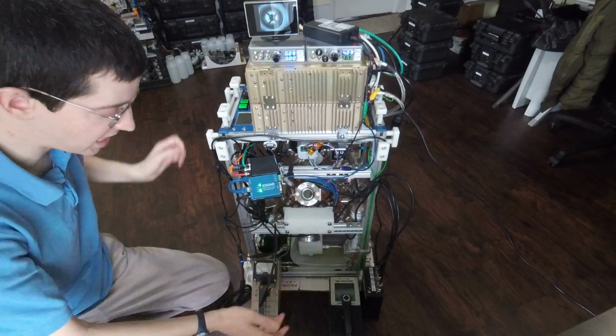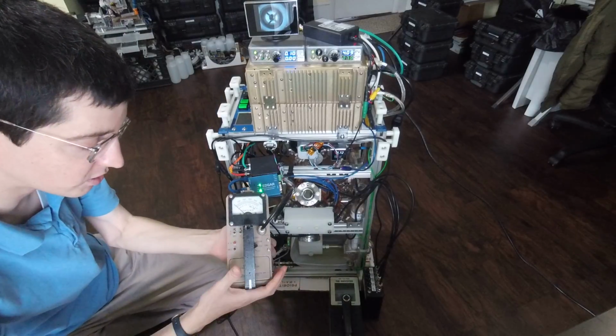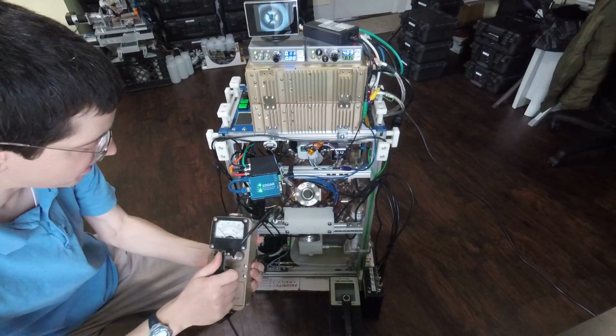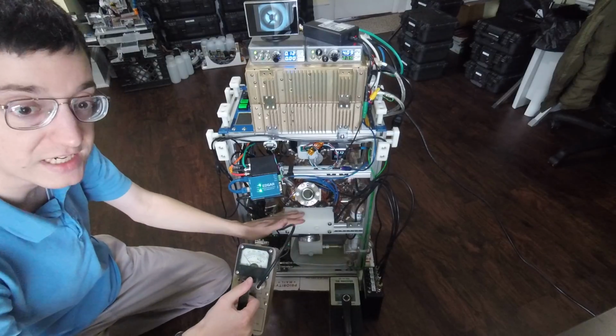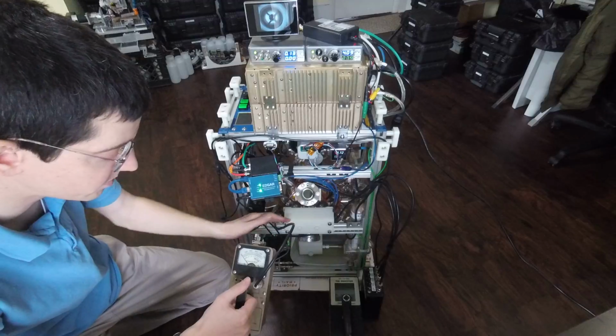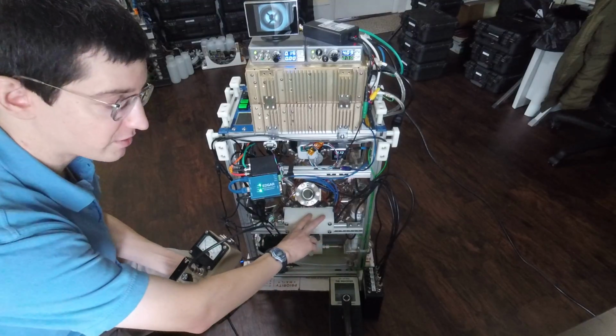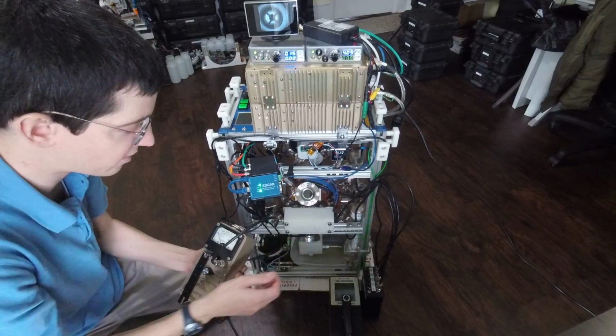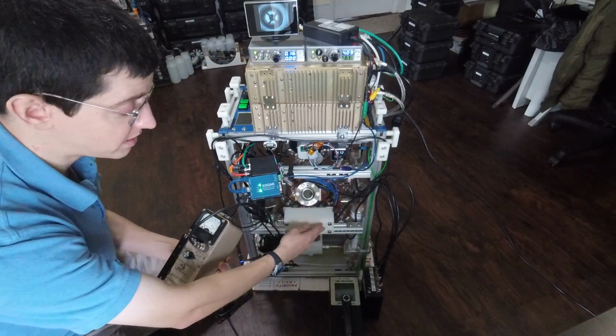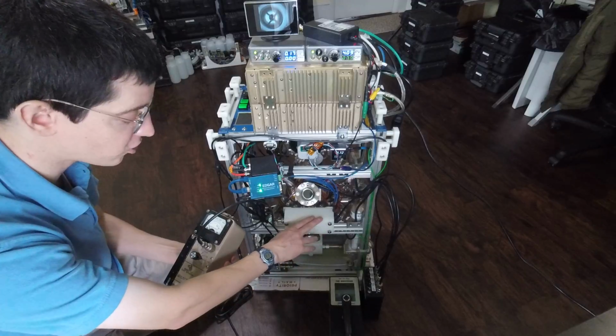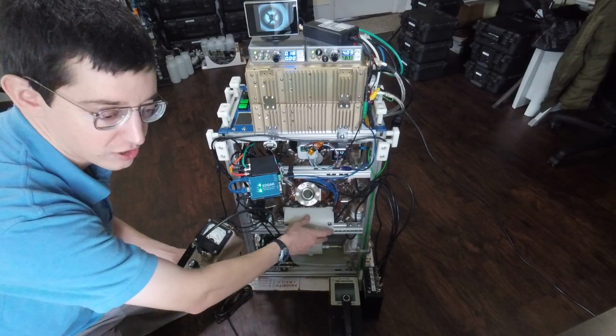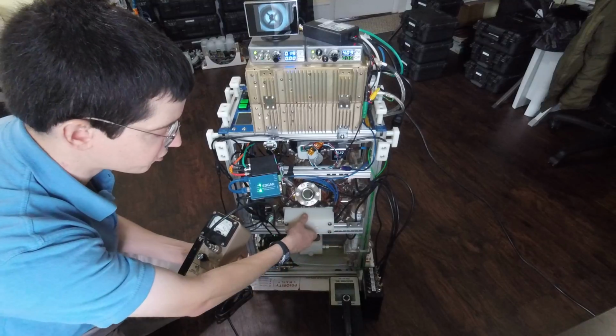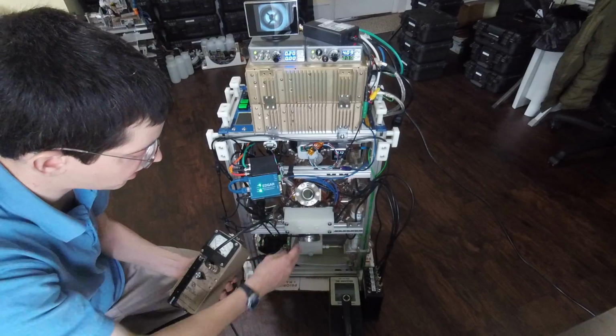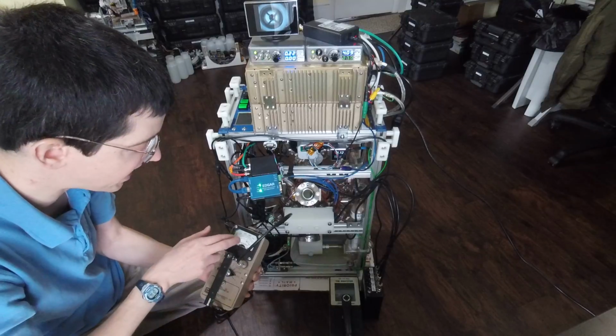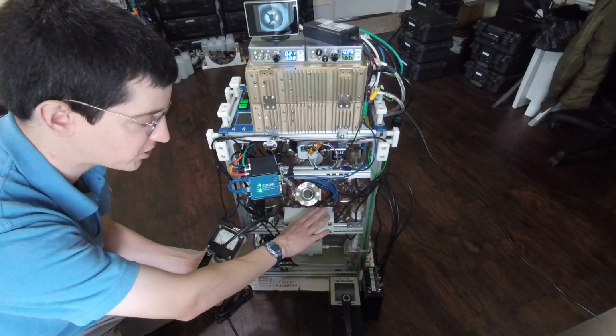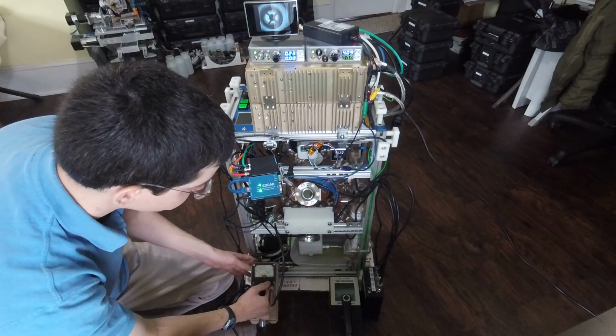So, some of the instrumentation I have with me today: I have the Ludlum Model 12 rate meter, connected to a Nancy Wood G10-2A boron trifluoride tube. I'm continuing to use the boron trifluoride tube over the newer helium-3 detectors I have, since the boron trifluoride tube generates a higher pulse height when it detects a neutron compared to the helium-3 tubes. Also, due to tube sensitivity, moderator geometry, and neutron energy, it just happens to work out calibration-wise that 1,000 counts per minute equals 1e6 neutrons per second, so that's a very convenient conversion factor.